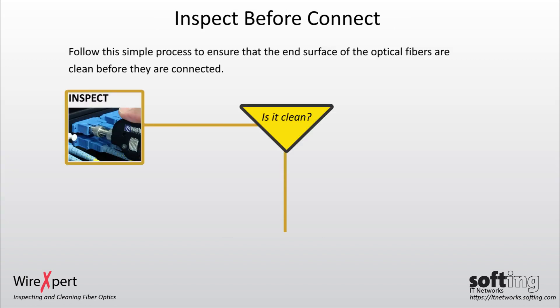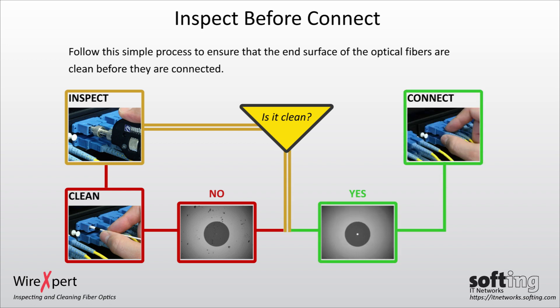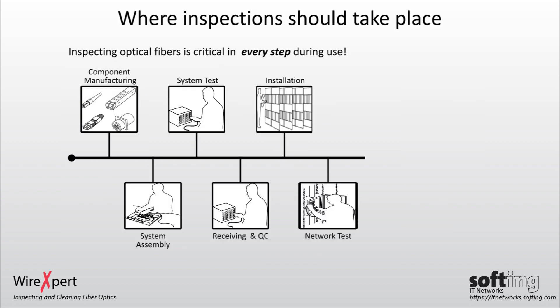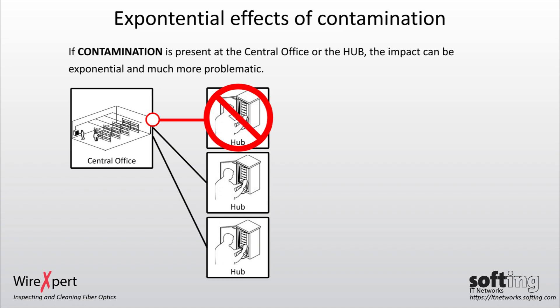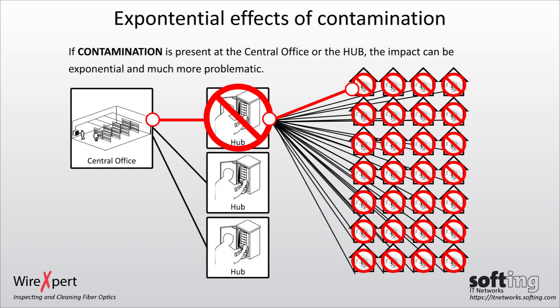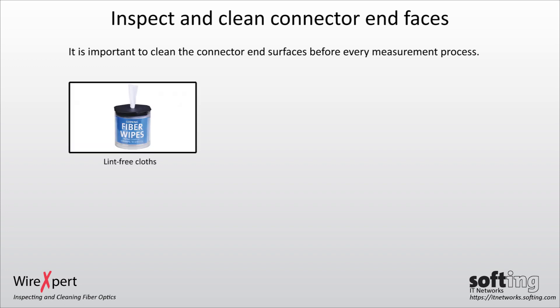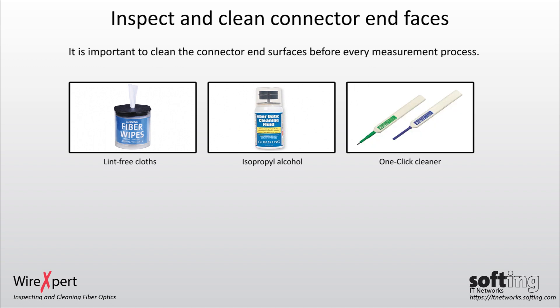Follow this simple process to ensure that the end surfaces of the optical fibers are clean before they are connected. Inspecting optical fibers is critical and should be conducted at every step during use. If contamination is present at the central office or the hub, the impact can be exponential and much more problematic. Therefore, it is important to clean the connector end surfaces before every measurement process. Use only suitable substances such as lint-free cloth, isopropyl alcohol, or the one-click cleaners provided in the fiber test kits.